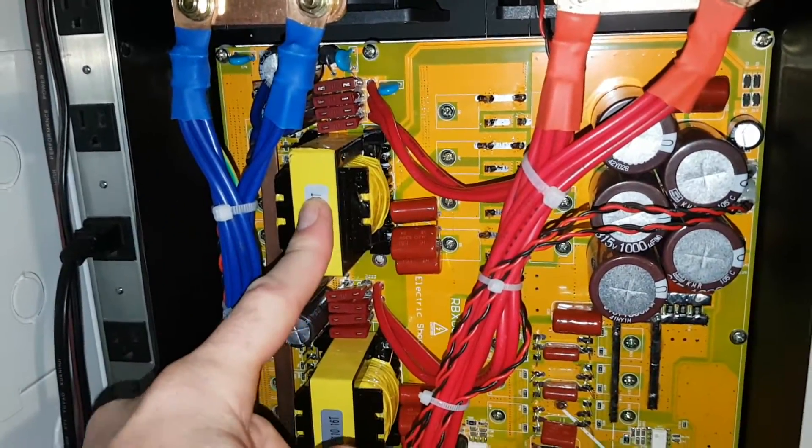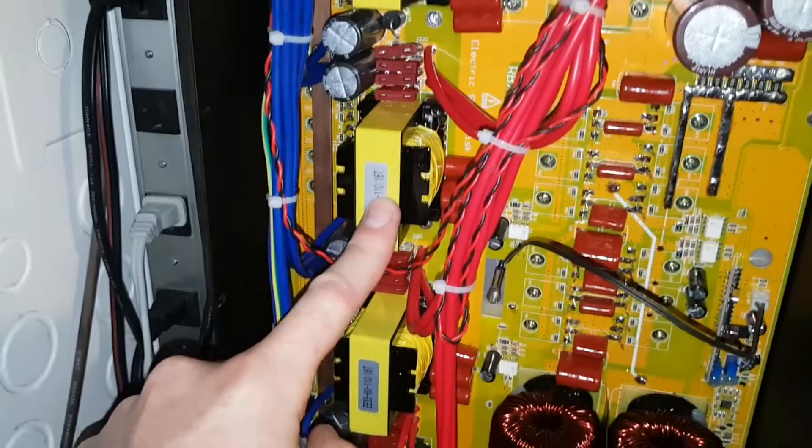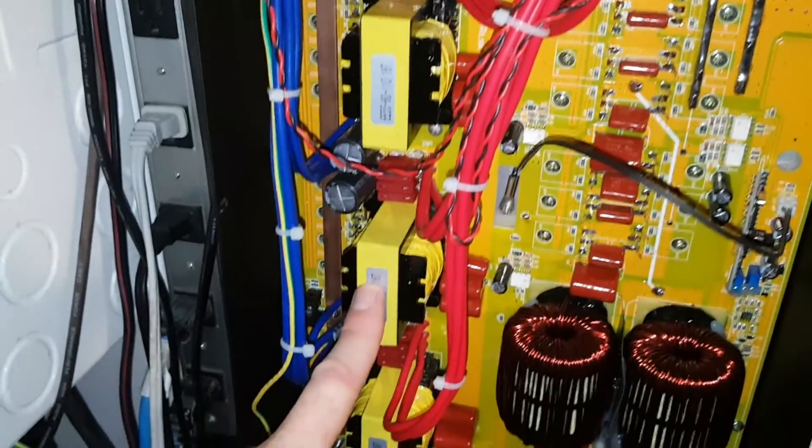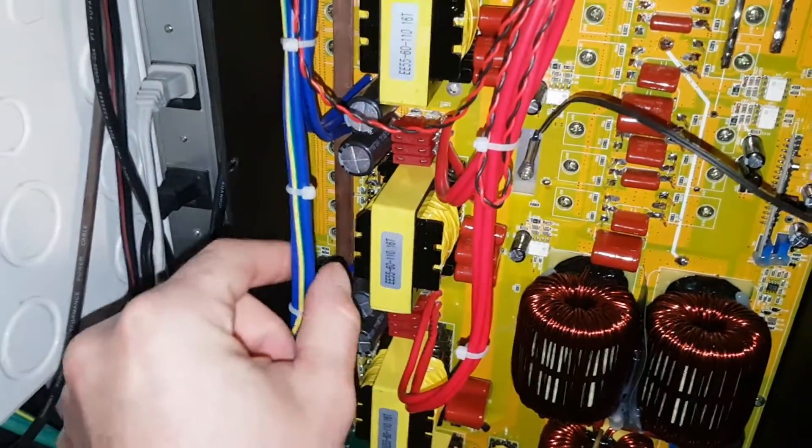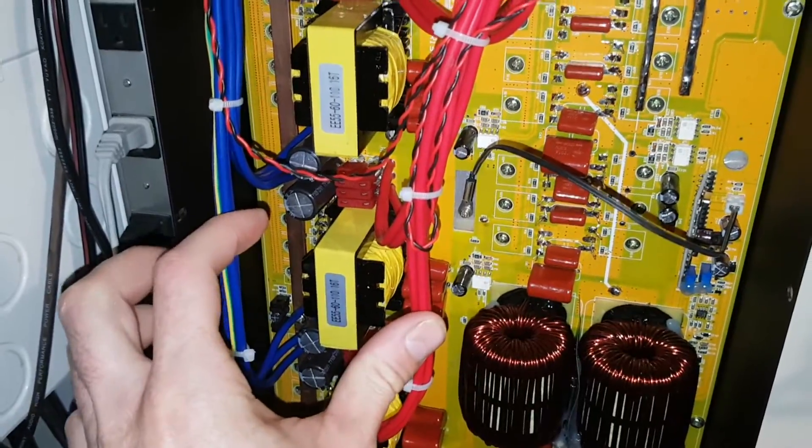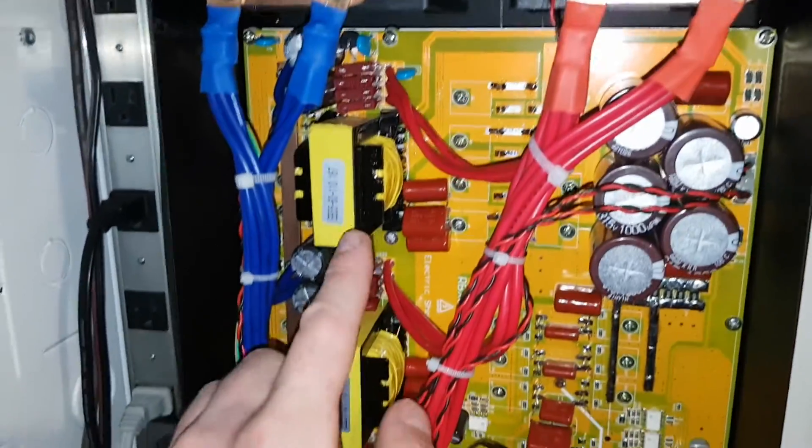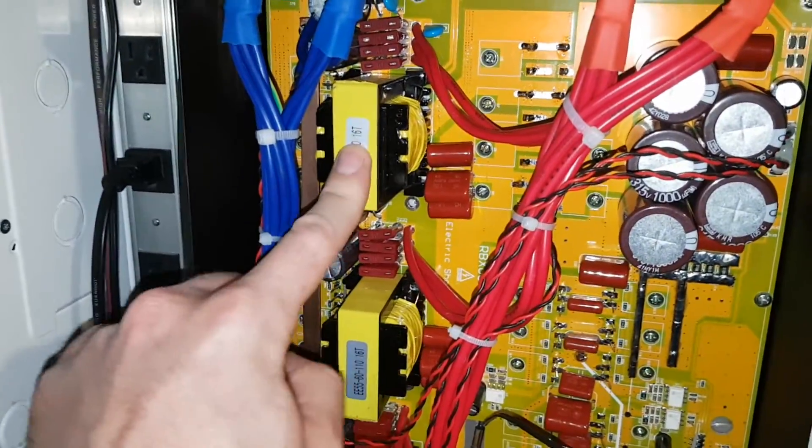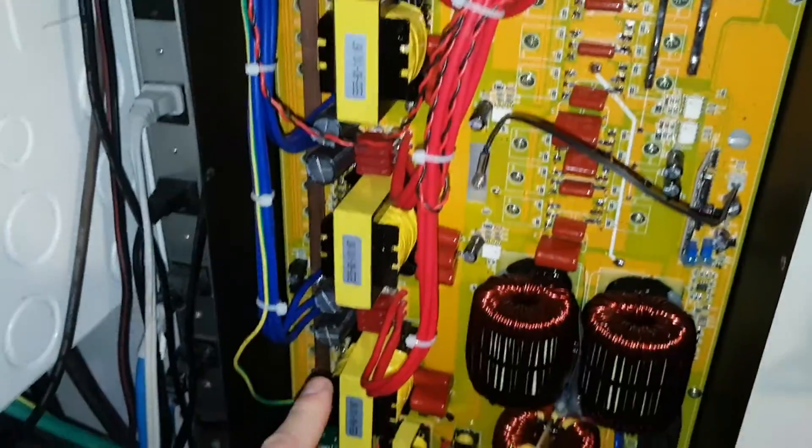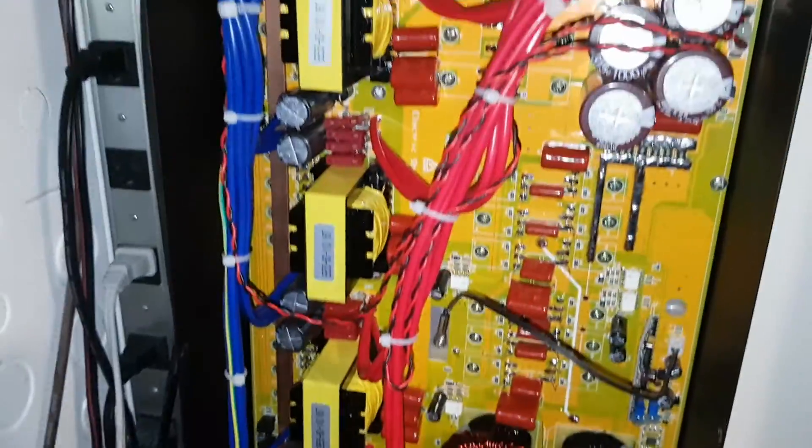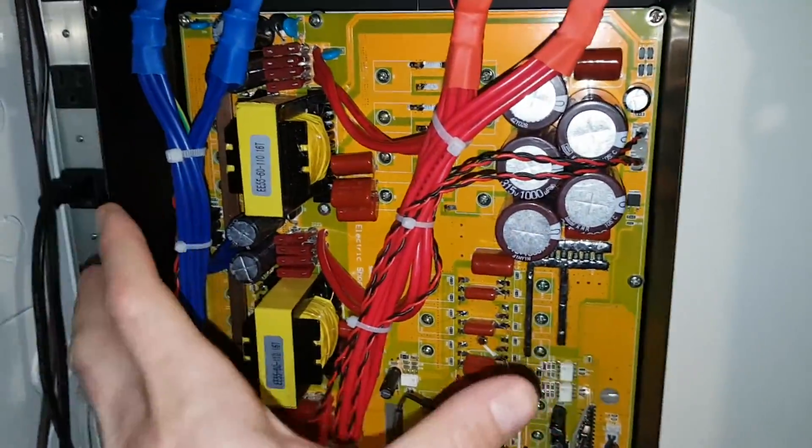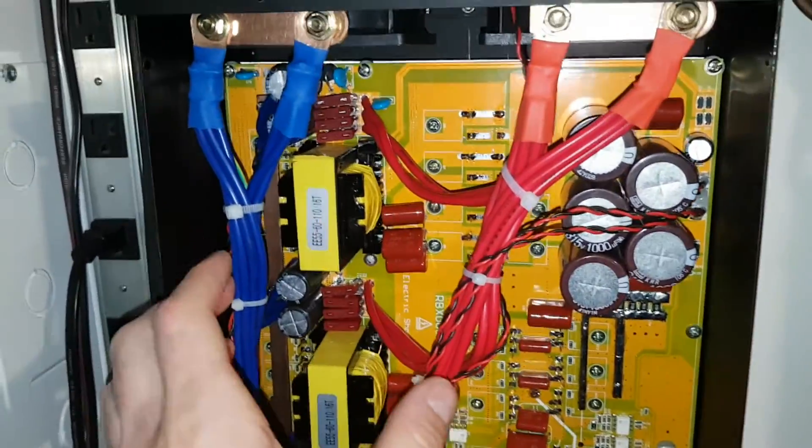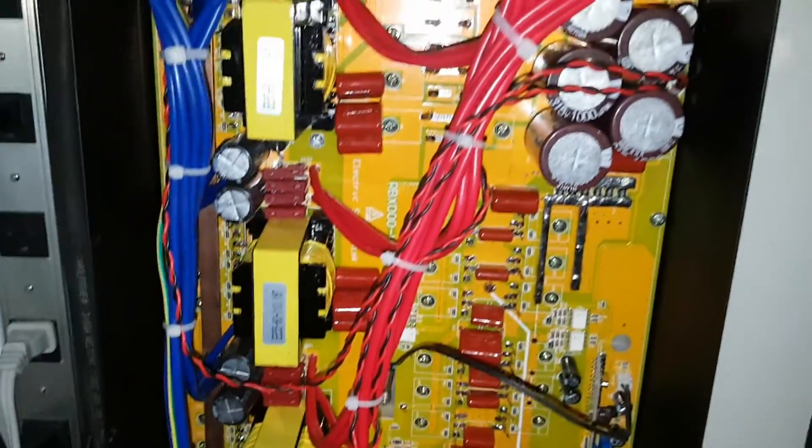Shortest wire, so this transformer is going to take the most current. This one's going to take the second most current, third most current, and least amount of current, because these wires are longer, they have more resistance in them. So between this one, this one could take 20% more current than this one.